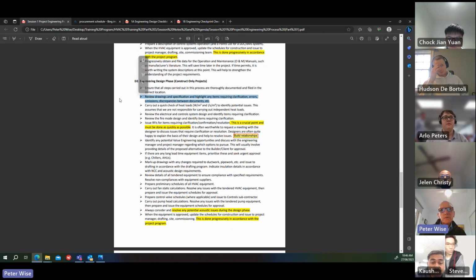Go through the drawings and specification and highlight any items requiring clarification, any errors, omissions, or discrepancies between documents. Sometimes you look at the drawings and then the spec - a good example is a fan. You look at a fan on the drawing and it adds up to 500 litres a second, but the spec says 1,000 litres a second. There's a discrepancy between the documents. You need to note that down, make a list of any discrepancies, and issue an RFI to get them clarified.